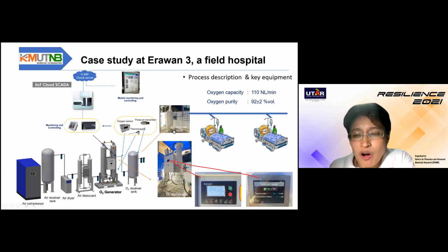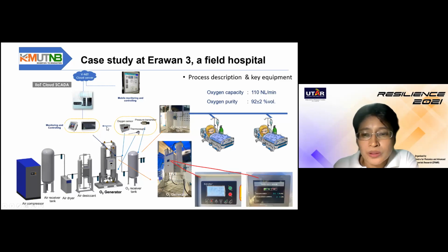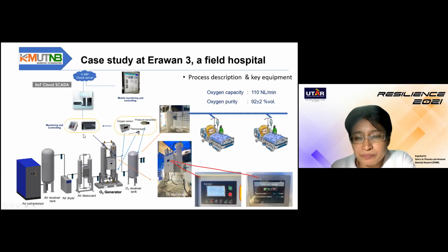At Erawan 3 Hospital, the concentrated oxygen was directly piped to each patient bed. The system was also equipped with an oxygen sensor, pressure transmitter, thermocouples, as well as a PLC. We also implemented a direct connection from the PLC to the cloud, and this enables us to remotely monitor and control the system.